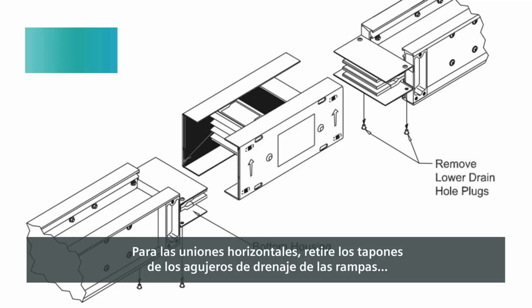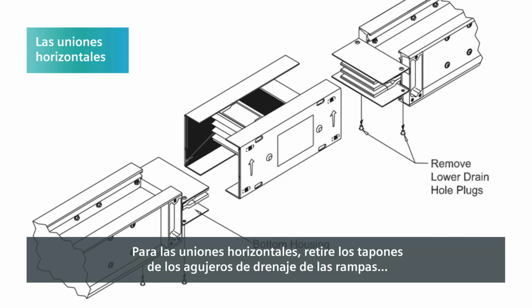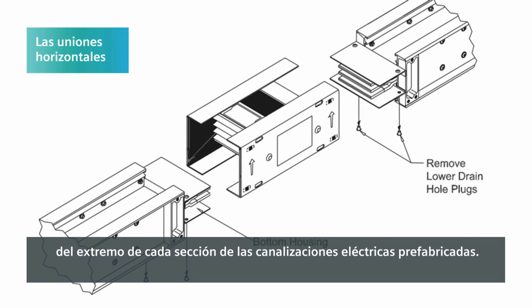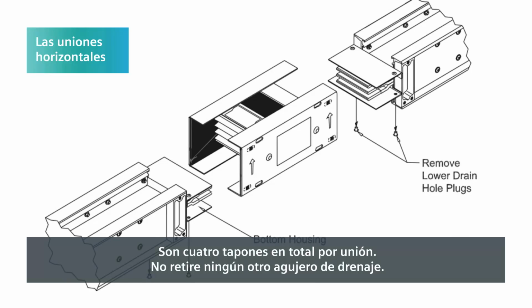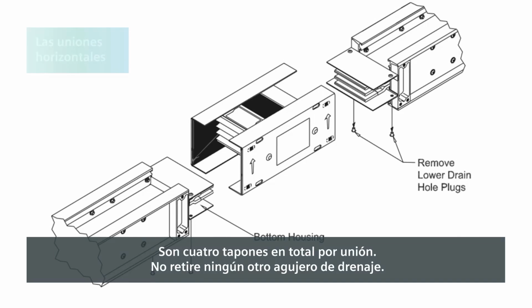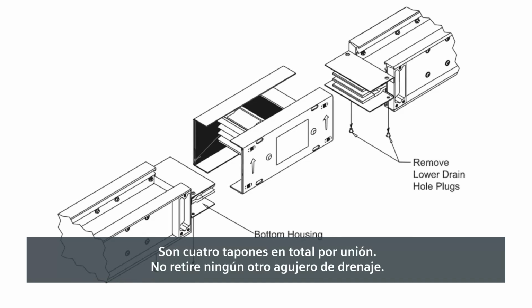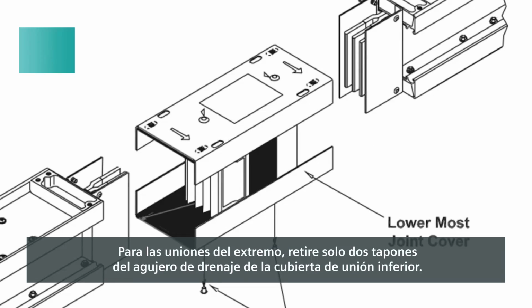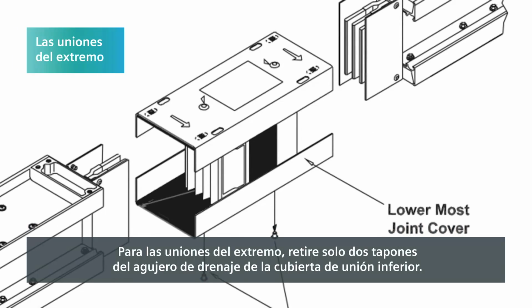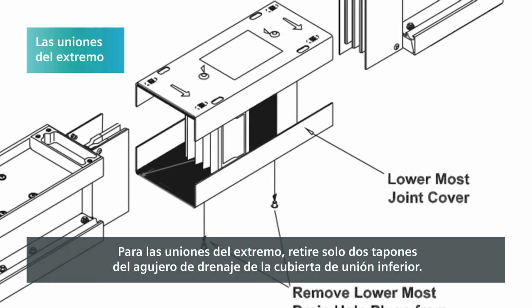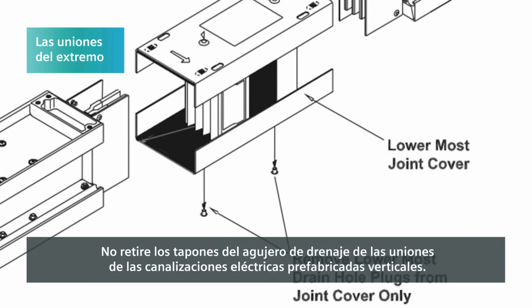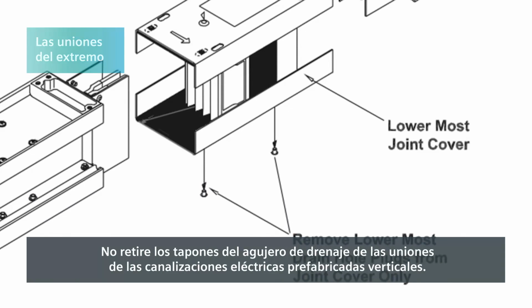For horizontal joints, remove the 2 lower drain hole plugs from the end ramps of each busway section. This is 4 total plugs per joint. Do not remove any other drain holes. For edge joints, remove the 2 drain hole plugs from the lowermost joint cover only. Do not remove drain hole plugs from vertical busway joints.